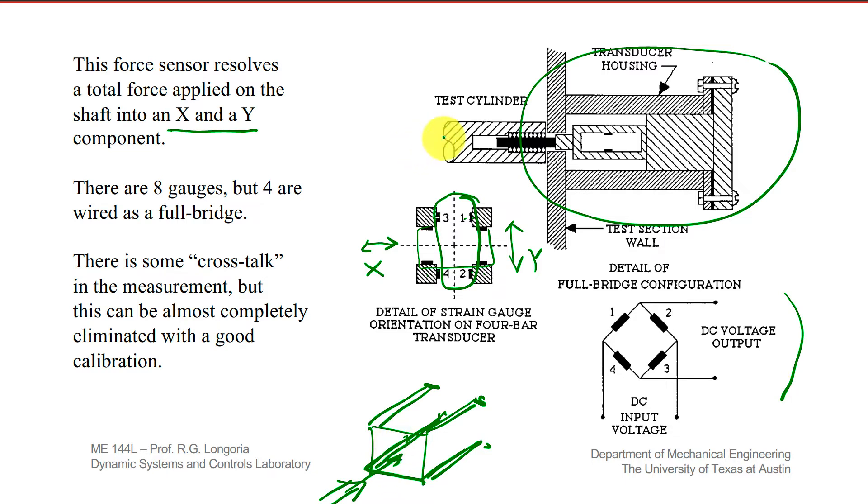So as you apply, this was holding a cylinder here, and as forces were put out of the plane of the page as well as up and down, you can measure simultaneously the XY forces. So again, there's two bridges there that are active, so you have two channels of force.